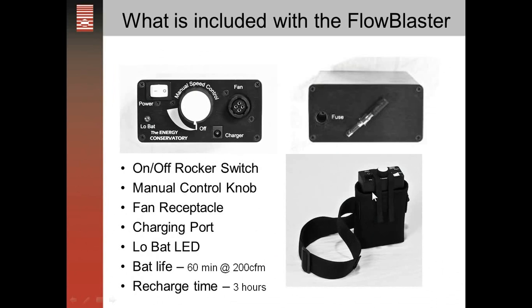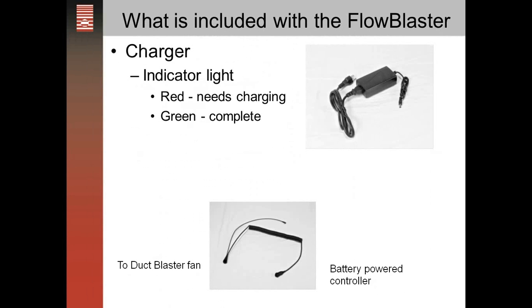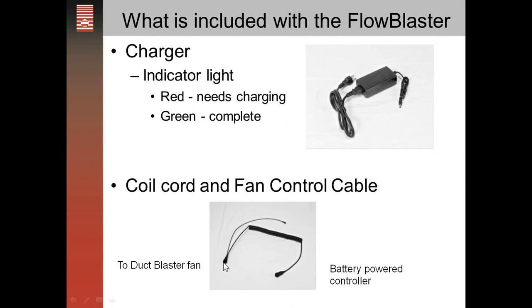The recharge time for the battery is about three hours. The charger has an indicator light — when you plug it into the wall and then into the battery speed controller, red indicates it needs charging and green indicates charging is complete. The coil cord connects the duct blaster fan to the battery-powered speed controller, and it also has the control cable that goes up to the DG700.